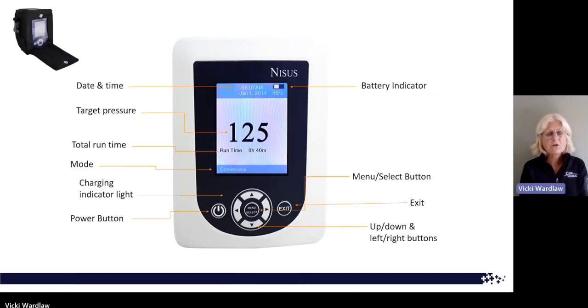So when the screen is turned on, what you see at the top is a battery indicator along with the percent of battery that is left. We have a date and time up there. In the center is your target pressure. That would be your prescribed pressure or your prescription from your provider. These devices come from the manufacturer, from us, set at negative 125 millimeters of mercury, because that's typically what is ordered by providers, but you do have a range in this device from negative 40 millimeters of mercury all the way to negative 200 millimeters of mercury.